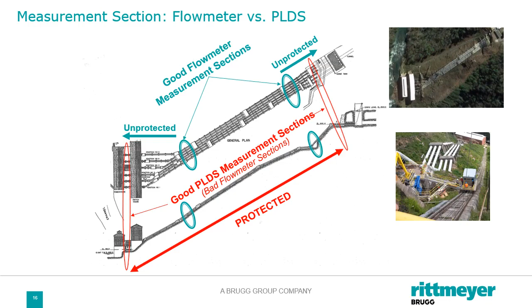So what are the effects of these poor measurement locations? Well, I've assembled some fictitious data in a spreadsheet just to illustrate this point. If the black line here is the actual flow, you can see that flow meters in a poor measurement section can face uneven flow distributions, which will vary as the flow rate varies. And so this brown line is similar to some of the things we've seen at a flow meter, for instance, near an intake. And the distortions can be quite big and the errors can be quite large. And again, they vary with flow rate.